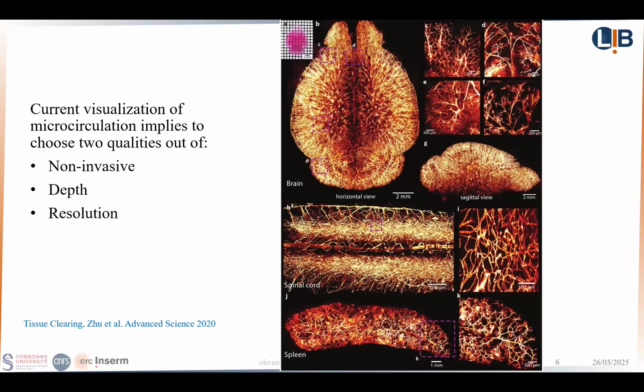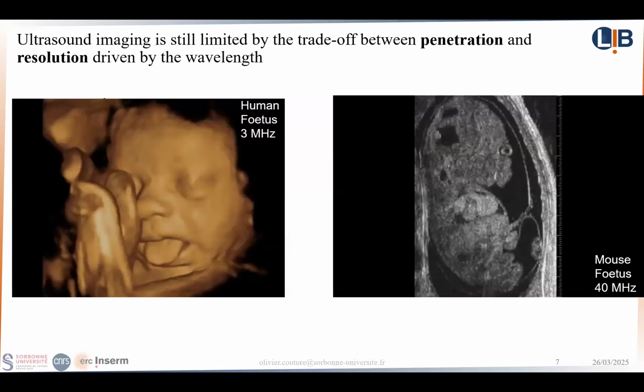So ultrasound has its own dilemma. The dilemma in ultrasound is between penetration and resolution. And this is driven by the wavelength. So basically, if we want to look at the human fetus, we will go at 3 megahertz, which is a wavelength of about 500 micron. And so that will allow us to see a fetus down to maybe 15 centimeter in depth, because the penetration will be enough.